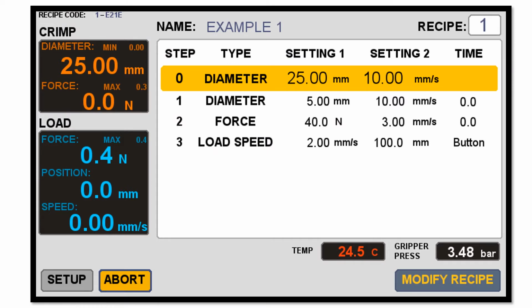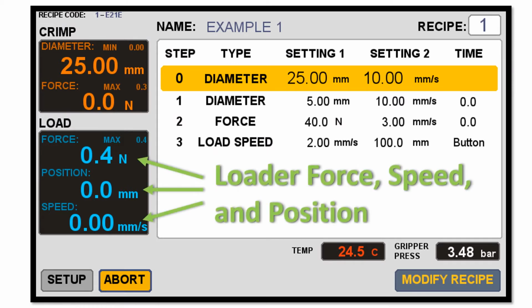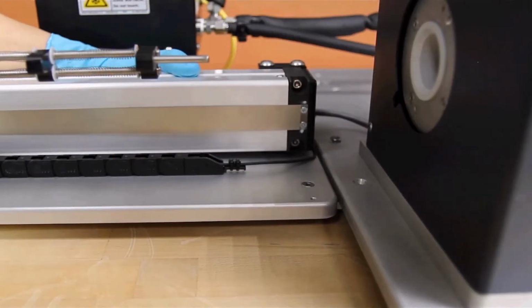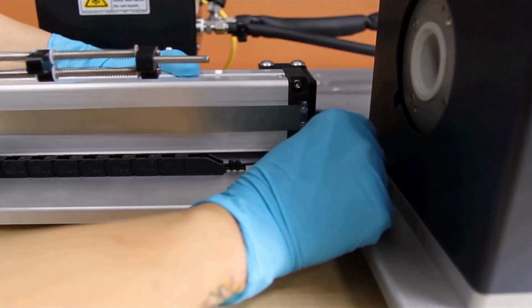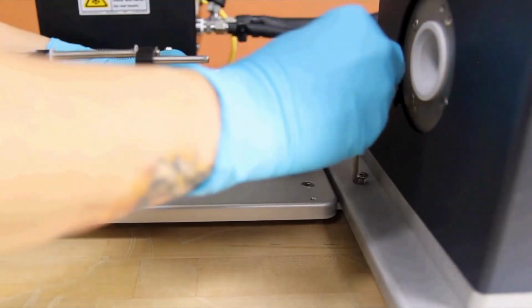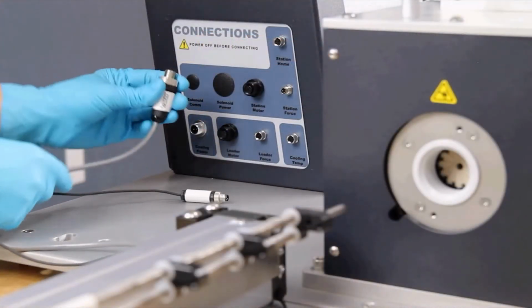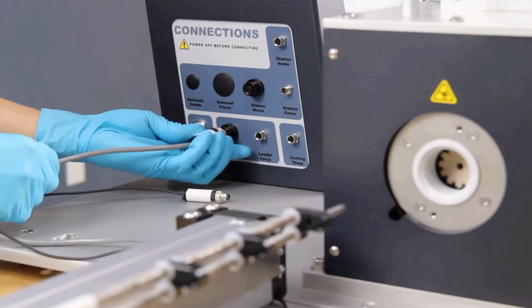The auto pushrod system gives force, position, and speed feedback. This ensures that you can control the force as well as the placement of your stent inside the catheter. To attach the system to the main base, install the two 10-32 flathead screws and connect the loader motor and loader force connection onto the machine side panel. The machine should always be off when connecting or disconnecting the attachment.